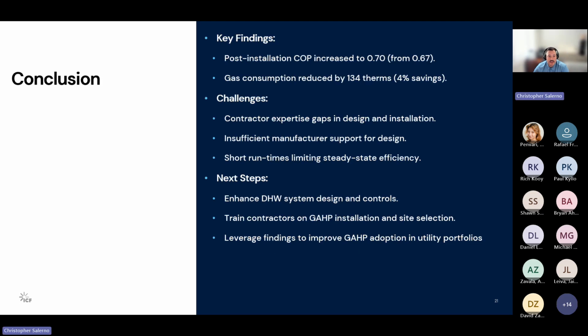At the end of the day, unfortunately, from what we found, the COP only increased from 0.67, which was our re-baseline, to 0.70, which only resulted in 134 therms, or 4% savings. The biggest challenges, as I mentioned: contractors really didn't know much about this, there were expertise gaps in design and installation, and there was insufficient manufacturer support, specifically with the specific GHP that we selected.